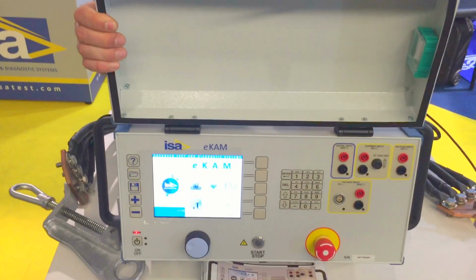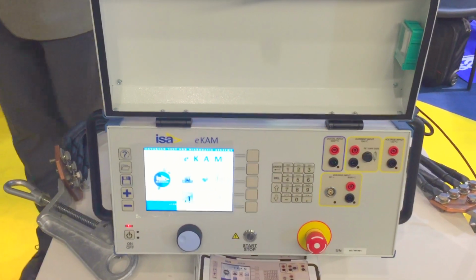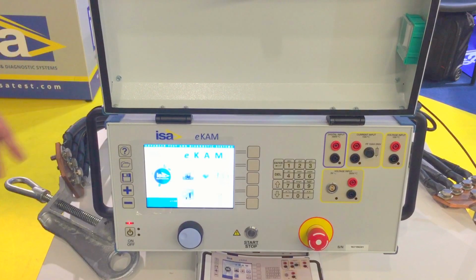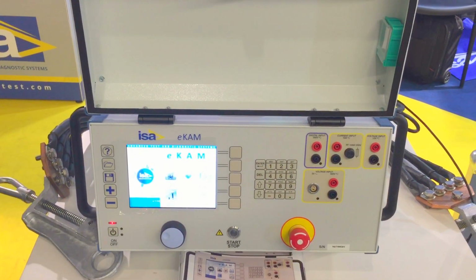The good thing about the test set is the fact that you can move this booster up to 20 meters from the device, and thus you can connect it maybe to a CT without the necessity of having forklifters to lift heavy primary equipment, which was standard in the past. With this device you can also do line impedance tests and ground grid testing, like step and touch voltage, which can be done with some additions.